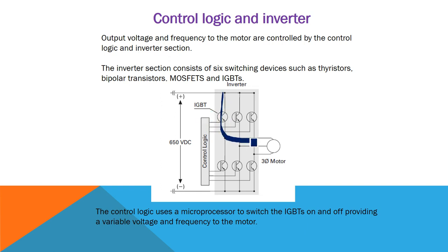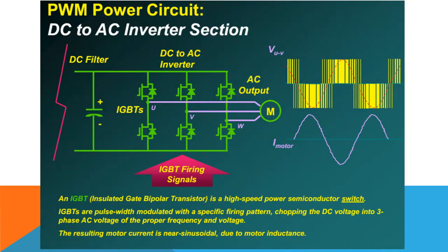When the switch is on, it will be giving a current to the motor. So in this picture, we will be seeing 6 IGBTs. By suitably switching them on and off, we will be sending current through its windings at sometimes in the one side and at sometimes in the opposite side. So it will be becoming what? AC, alternating current. So we are going to see the output waveforms generated. We already discussed this previously. We will be getting pulse width modulated AC.